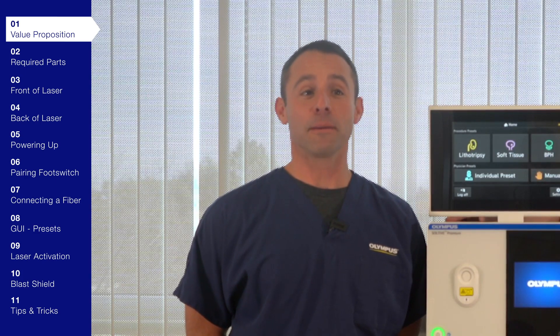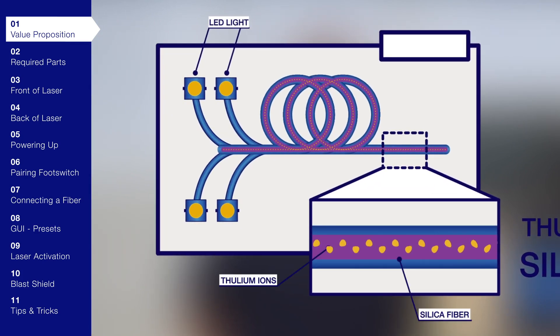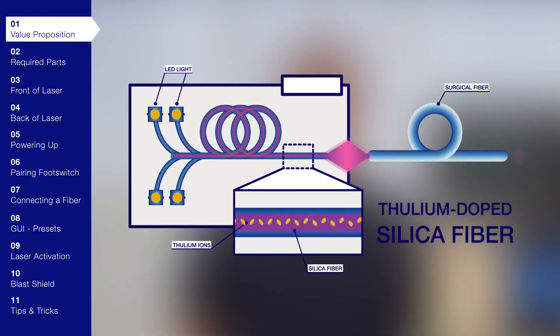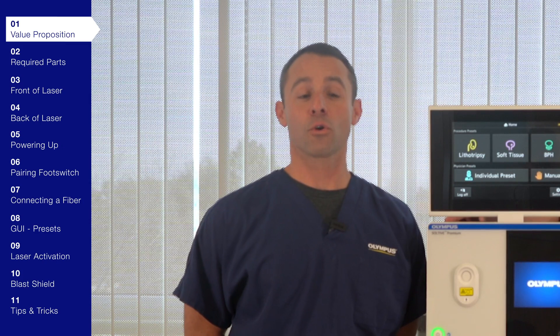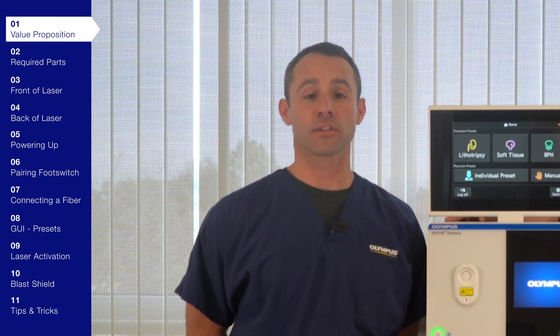So what is the SOLTIVE Thulium Fiber Laser System? The SOLTIVE Laser System is powered by a long, slim, internal fiber with thulium ions in its core. This inner fiber connects directly to a normal surgical fiber. The inner fiber is activated by light from LEDs, similar to those in a smartphone display. It's a striking improvement over holmium YAG systems, requiring far less power and maintenance upkeep to achieve better results.